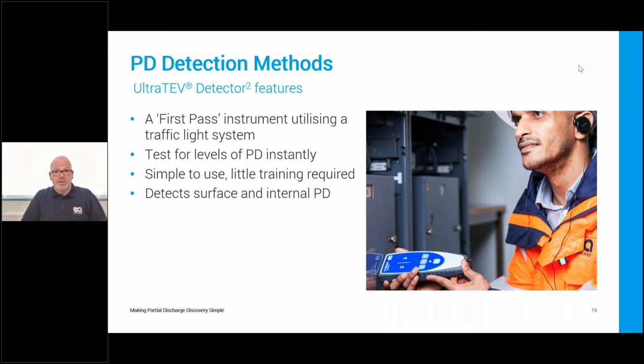The great thing about the detector is it gives an instant snapshot of the levels of PD activity. It really is very simple to use. Even I can use this one. And it does detect both TEV, so internal PD, and ultrasonic surface PD. It comes with a headset for when you're listening for ultrasonics. That really is the detector in a nutshell. It's pretty straightforward, but highly effective as a first pass level of PD detection.